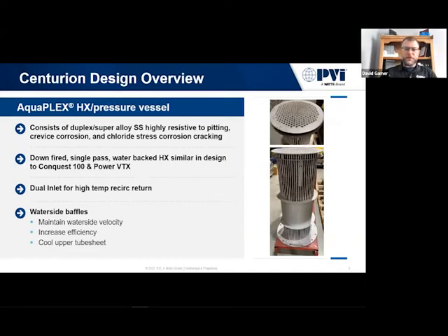The heat exchanger itself, if anyone's familiar with the Power VTX, this is a very similar design where it's a vertical fire tube. The tubes are a little bit smaller and we have more of them in there, but the heat exchanger itself is our Aquaplex material. It goes through the same pickle and passivation process that I believe everyone's familiar with. And we have our dual inlet for that dedicated building recirculation return line.